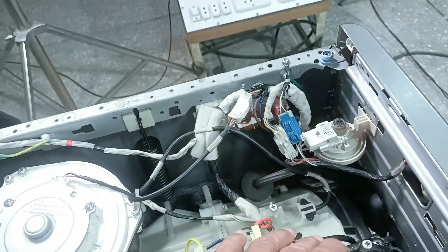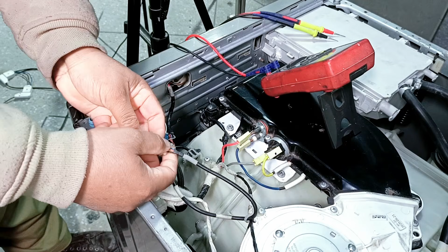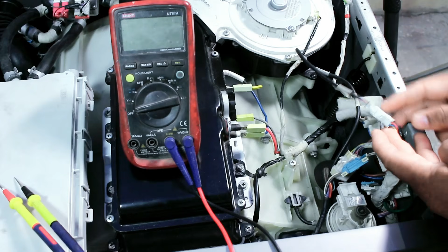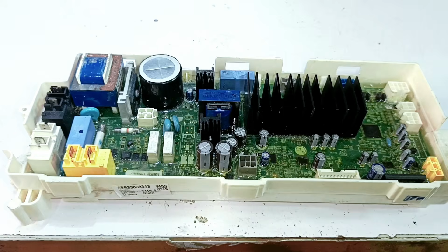But if, for any reason, this sensor itself has gone faulty, then we will check it as well, how it works and how it can be tested. If the sensor connector is properly connected and the error still appears, then it is possible that the sensor is internally faulty. The easiest method is that if you already have this sensor available, replace it, and there is a strong chance that the error will be resolved. Another possibility is that even after replacing the sensor, the issue still remains. In that case, the problem may be in the main PCB.